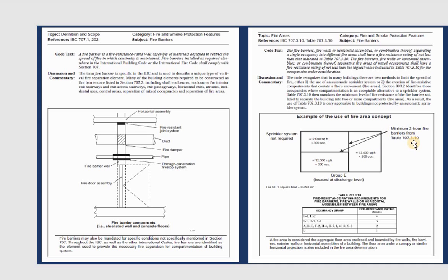How do you know whether it's two hours, three hours, or one hour? This is from Table 707.3.10, which shows the occupancy group and how many hours you need for the wall between them. For example, H-1 and H-2 — both hazardous — require four hours. So much danger, which is why hazardous occupancy groups are so hard to design and require four hours for fire resistance.